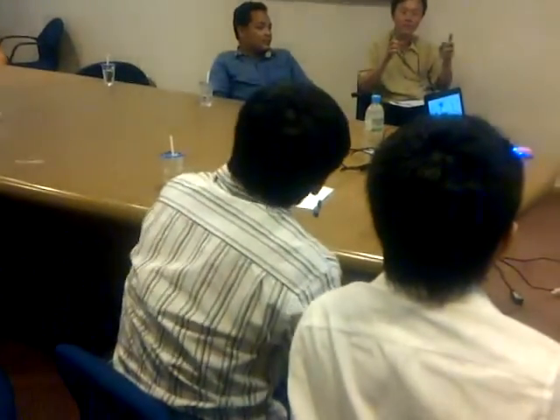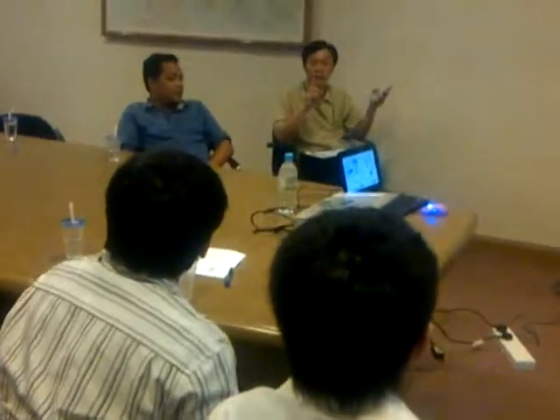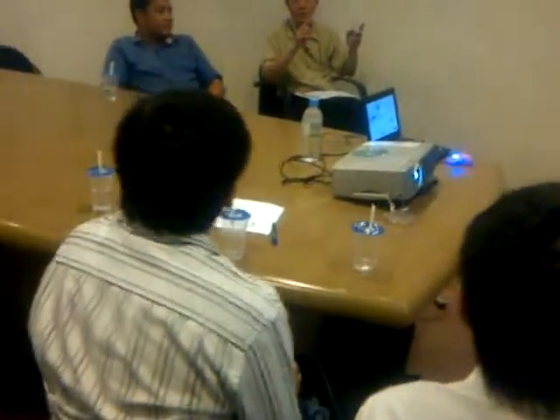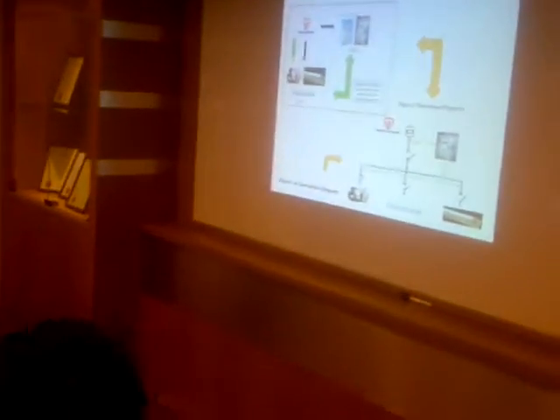It can be double backup — backed up by battery in real time, so there is no power interruption. But when the genset backs up, it could be 15 seconds later when there's a power failure. Within that time the genset cannot pick up so fast because you need to crank it up, and it takes time for the current and voltage to stabilize. So normally 15 seconds — within this time you need battery backup, or else all your data will be lost. That's data center, ICT.